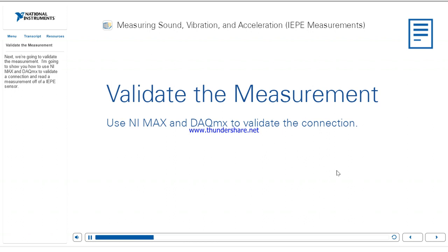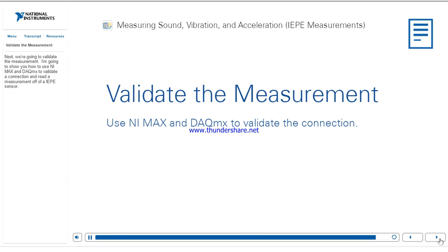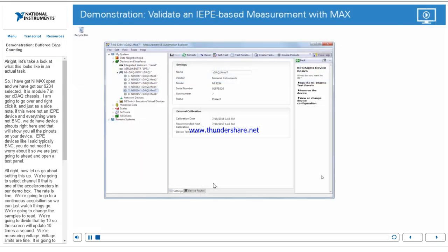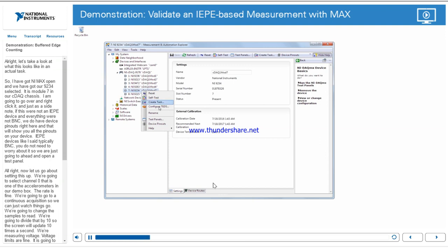Next, we're going to validate the measurement. I'm going to show you how to use NI MAX and DAQmx with an IEPE sensor. I've got NI MAX open with our 9234 selected — it's Module 7 in our cDAQ chassis. I'll right-click it, and just as a side note, if this were not an IEPE device, we do have Device Pinouts here to show all pinouts on your device. IEPE devices, as I said, are typically BNC, so you don't need to worry about it.